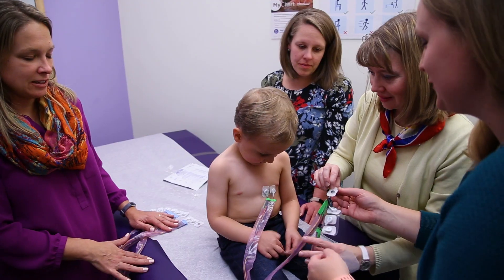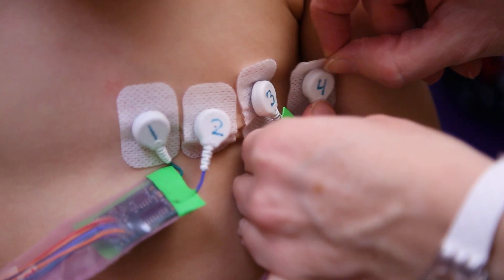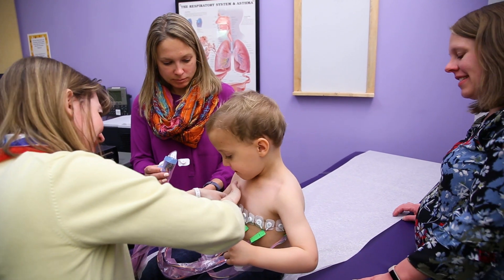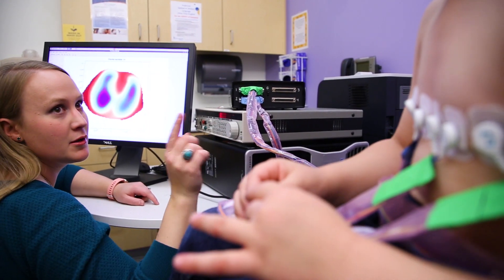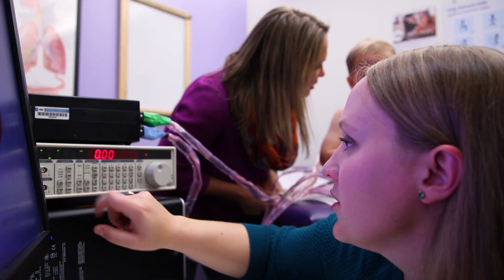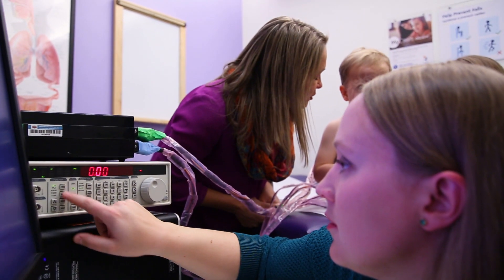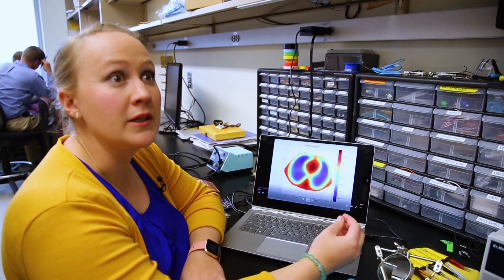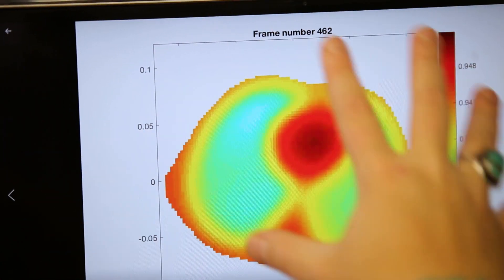In EIT, you're flowing very small currents into the body. You have a band of electrodes — you decide what plane or slice you want to look at, and that's where you put the belt onto the person. The electricity flows in, and you measure the voltage. Your tissues resist the flow of current, so you measure the electrical potentials at that plane. Because air doesn't conduct electricity, it makes it easy to detect regions where air is trapped or ventilation is poor.